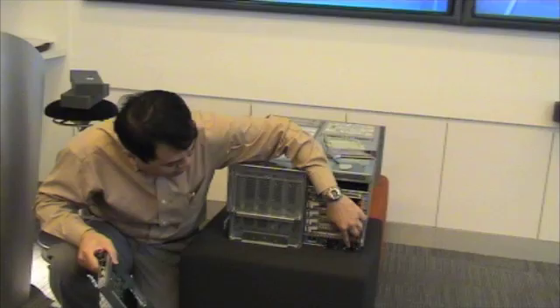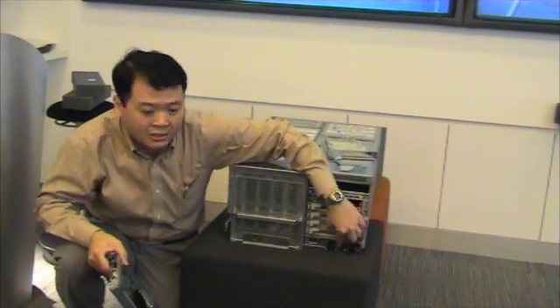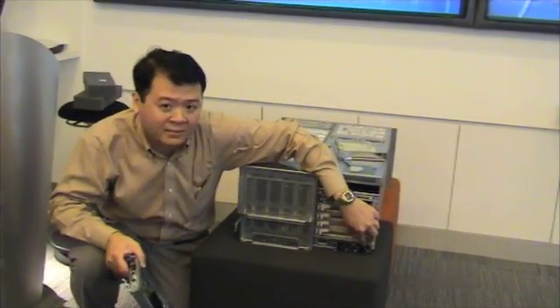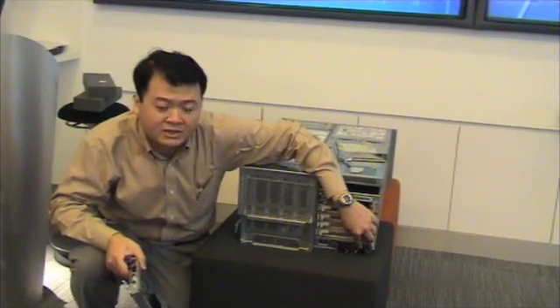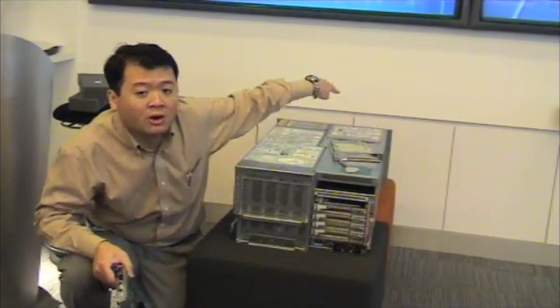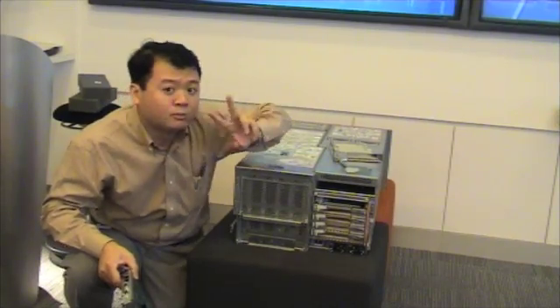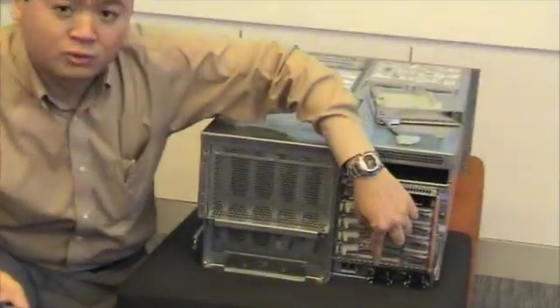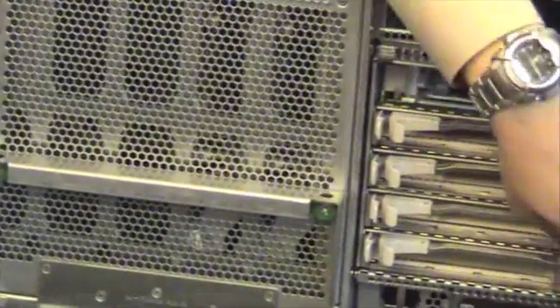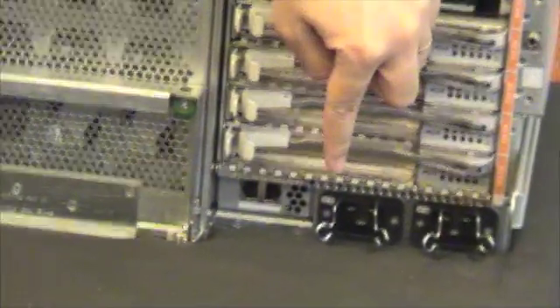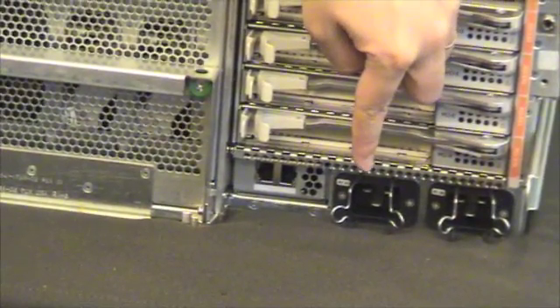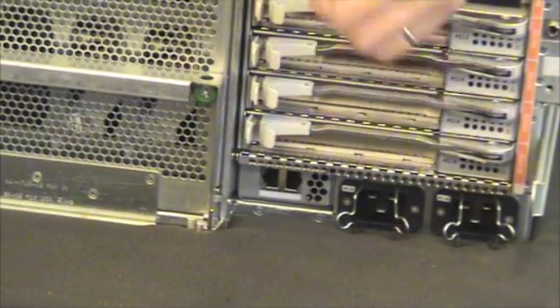Another piece that you need to take note of is the power supply. We're looking at two C19 power supply inputs. Each one of these goes to an individual power supply in front, one to each power supply. So if one is to fail, the system will continue with the other. It's a 1+1 configuration. Thank you.